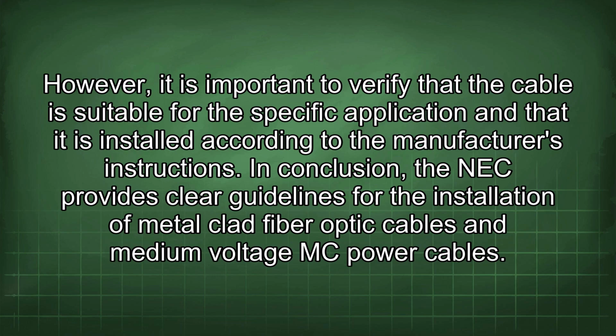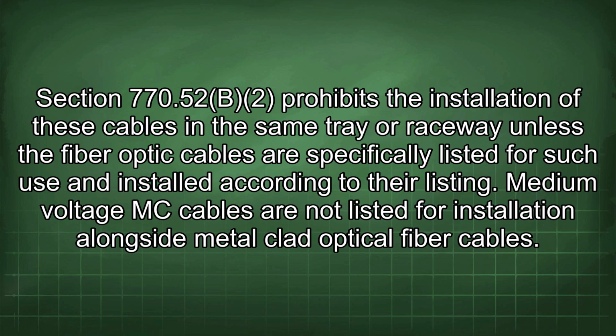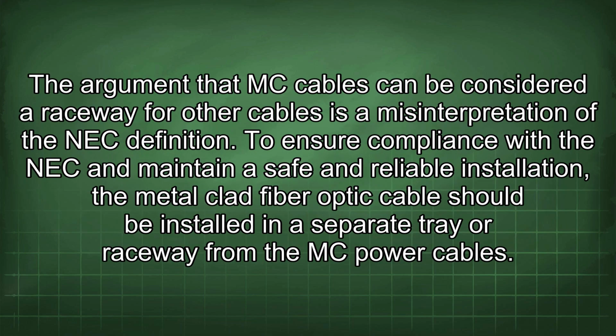In conclusion, the NEC provides clear guidelines for the installation of metal-clad fiber optic cables and medium-voltage MC power cables. Section 770.52(B)(2) prohibits the installation of these cables in the same tray or raceway unless the fiber optic cables are specifically listed for such use and installed according to their listing. Medium-voltage MC cables are not listed for installation alongside metal-clad optical fiber cables. The argument that MC cables can be considered a raceway for other cables is a misinterpretation of the NEC definition.